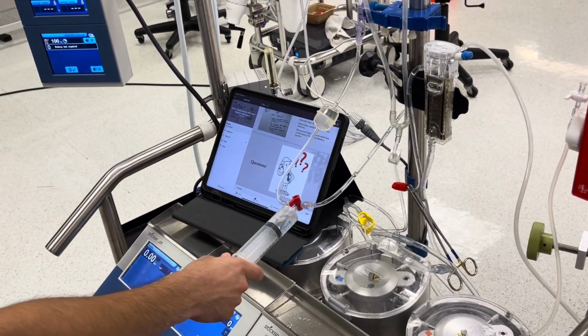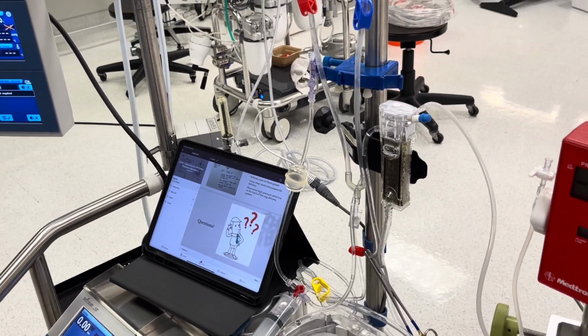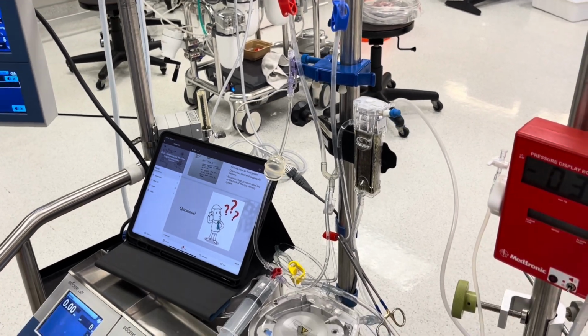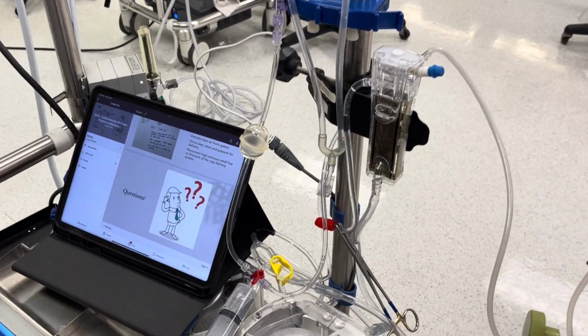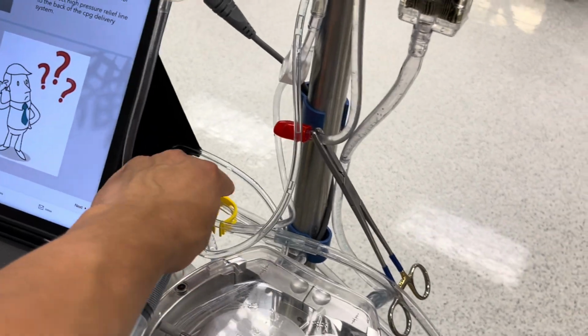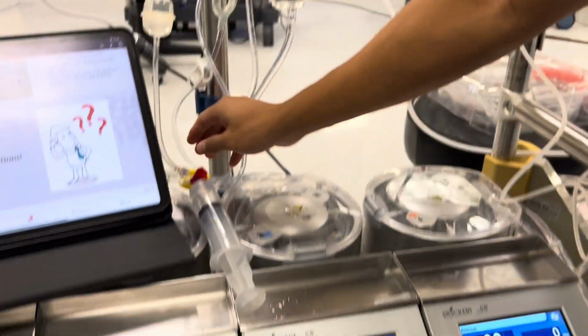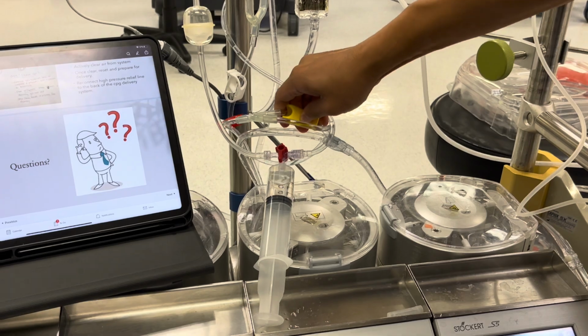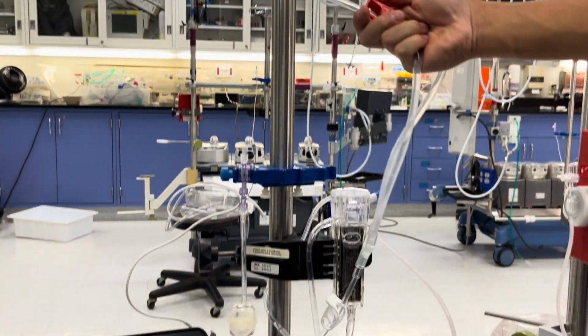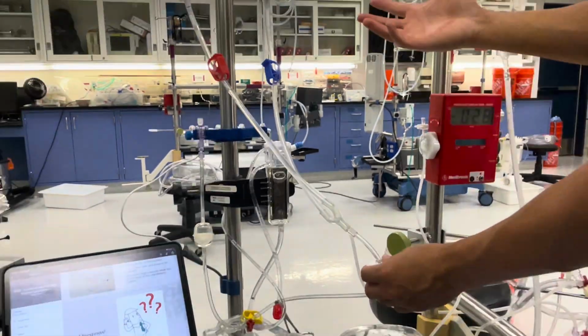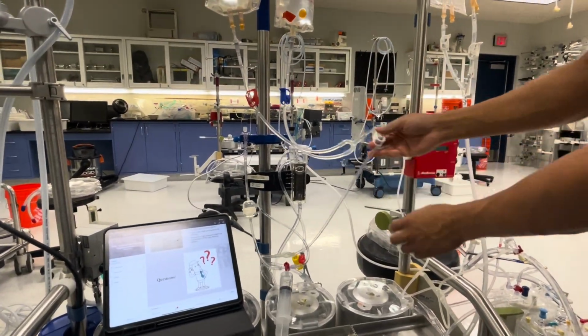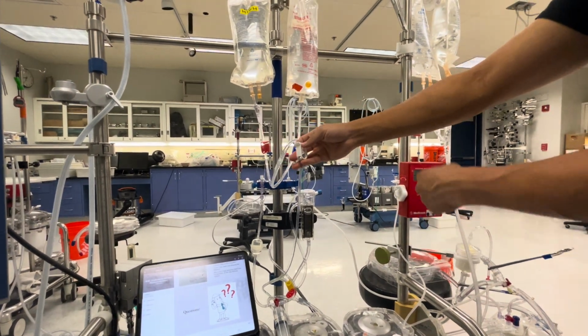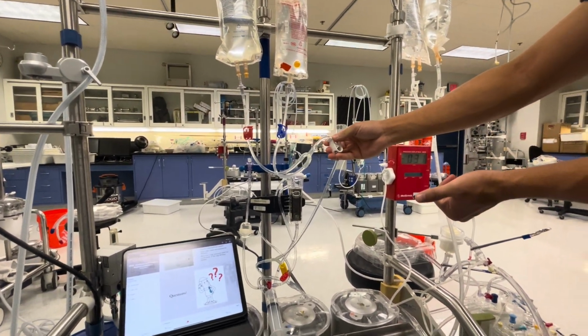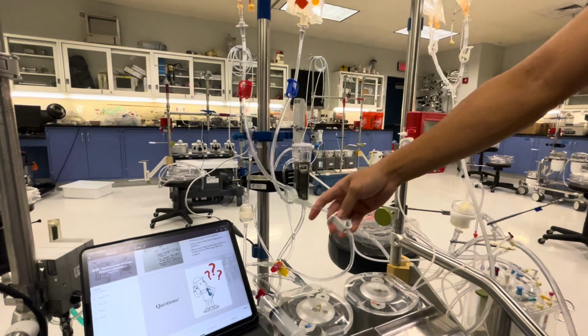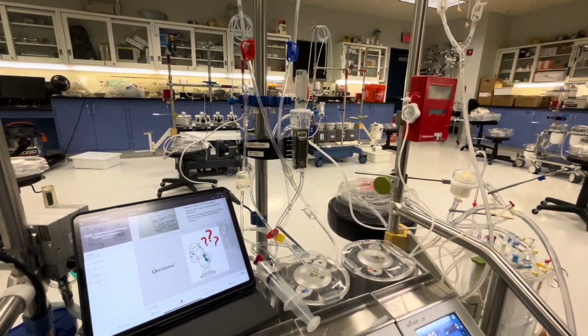Okay, yeah. So right before you finish, the next step would be to make sure the bridge is closed. Make sure the bridge is closed and your high K line is open, and make sure it's closed here. This way you're ready to deliver high K when the surgeon asks for it. And yeah, the bridge is closed when you're delivering, open for priming and hot shot. But after that, you should be good.